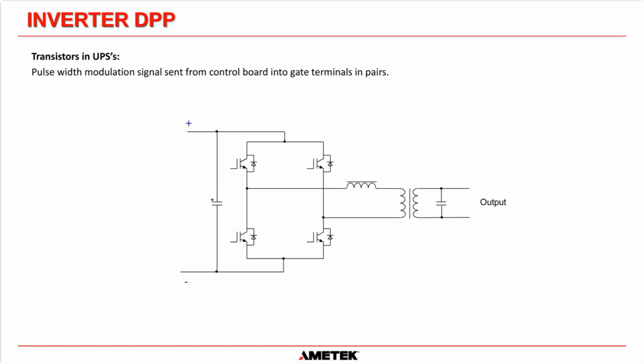The bypass supply will come from a transformer in your MCC, and that is a very robust, stiff power source, and that will supply a lot of current into that short circuit, which will then trip that breaker, and then when everything is good, you can transfer back to inverter. Okay, we're protecting the IGBTs.